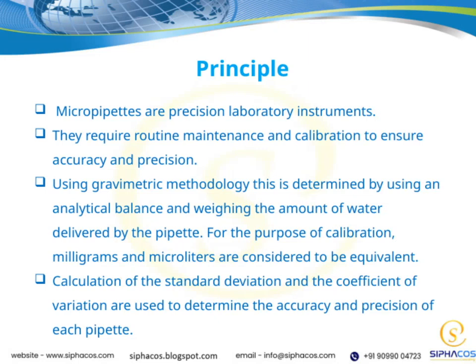Micropipettes are essential tools in the lab, and they are designed to be very precise. To make sure they keep working accurately, routine maintenance and calibration are necessary. Calibration, in particular, is about verifying that the pipette delivers the correct volume each time. One common way to do this is using the gravimetric method. Basically, we use an analytical balance to weigh the water that the pipette dispenses. Since water's density is well known, we can confidently say that the weight in milligrams corresponds to the volume in microliters. This means, for calibration purposes, milligrams and microliters are considered equal, simplifying the process.